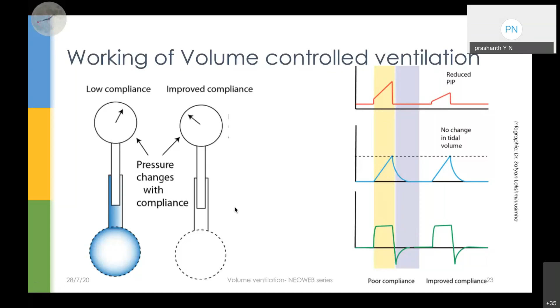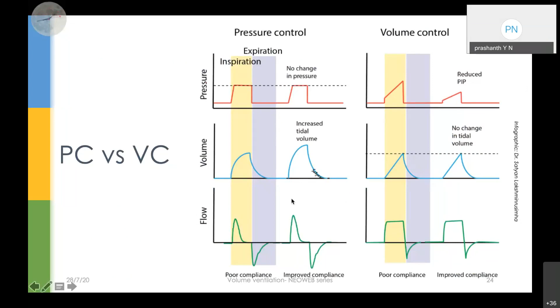All right, so let's move on to this. With an understanding of the working of volume control ventilation and pressure control ventilation, let's look at the difference between them. This is just a graphical representation of what we just discussed. Here in pressure control, we are looking at only the pressure. We are controlling the pressure, so your volume will become dependent. In volume control mode of ventilation, your volume is what we are controlling. We are telling the ventilator what to do in terms of volume, and your pressure will become dependent in this.